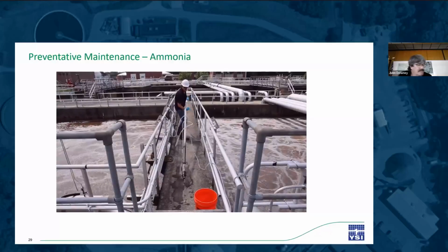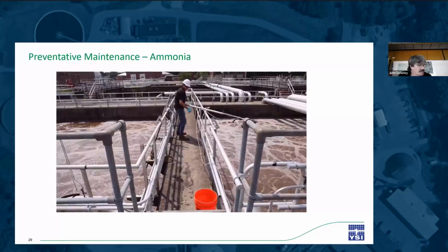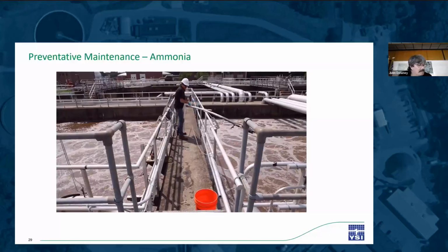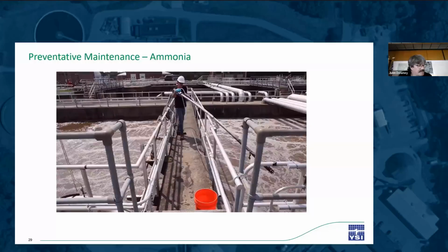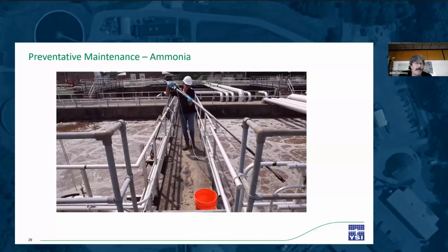That schedule is based on my experience with multiple vendors over 20 years. The reference junction fouling is really minimal, owing to the fact that we have these at the effluent of the basin. The nitrate sensor cleaning can be a lot more involved, requiring weak acid, isopropyl alcohol, Edisonite, or all three. It's very much an ad hoc operation, as I said.